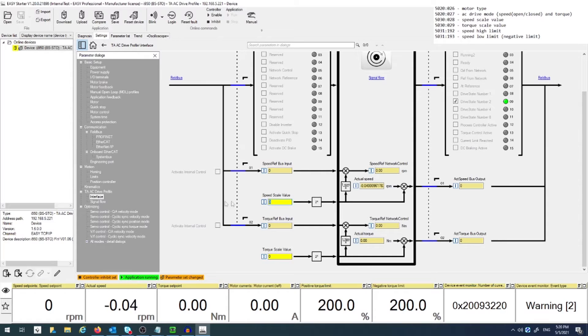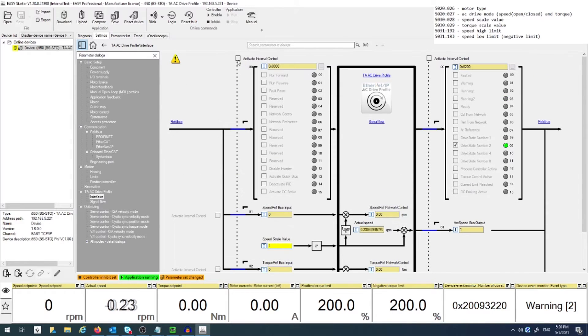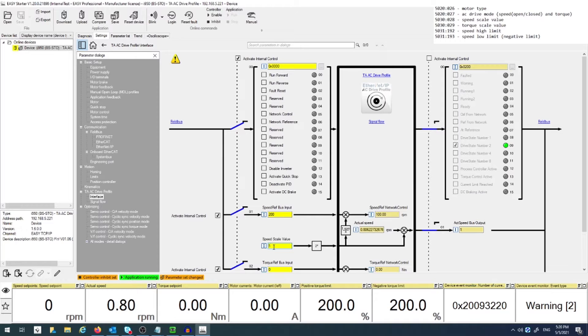Changes here reflect the input reference speed coming from the PLC. For example, if you were to change this value to 1, then 2 to the power of 1 is 2, and so the actual speed going out will be half of what is coming in. Keep in mind that this will affect the minimum and maximum speed range.